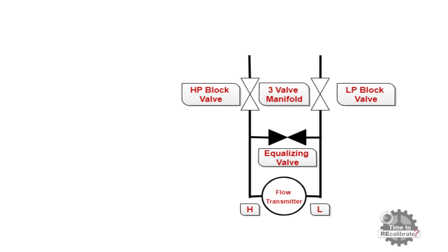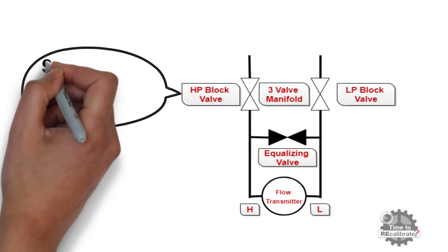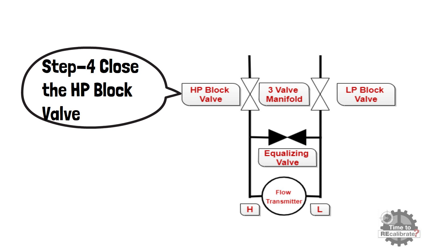In fourth or final step, close the HP block valve by rotating valve in clockwise direction. This will isolate the transmitter from the high side pressure. The transmitter has now been removed from service. In other words, once you have done with fourth step, you can remove transmitter without causing any damage to cell.